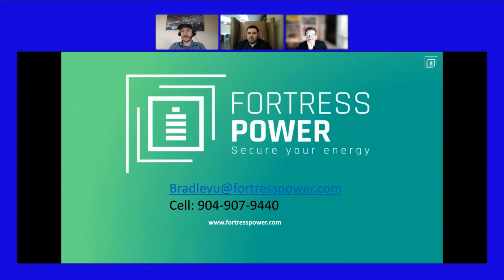What is the battery voltage of the inverter? It depends how many battery modules you have. With each module, you're adding 48 volts. The starting is 144 because you cannot get the Avalon with less than 3 battery modules. 3 battery modules, 48 volts each, would be 144 volts. By adding more modules, you increase the voltage. Once you top out on the stack, with 6 battery modules, that's 288 volts. When you add the second stack, which also has 6 modules, the voltage doesn't change, because the stacks connect to each other in parallel, whereas the modules connect to each other in series.